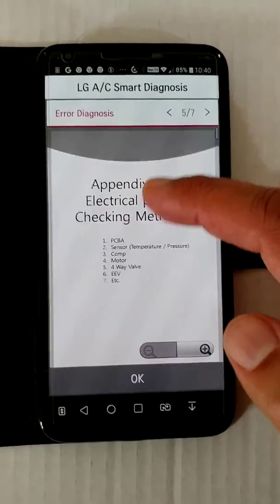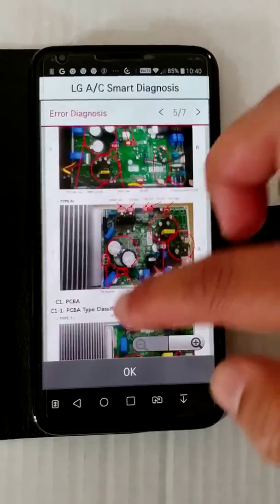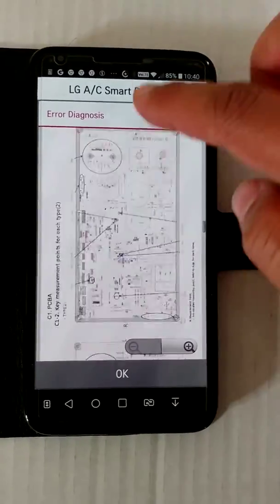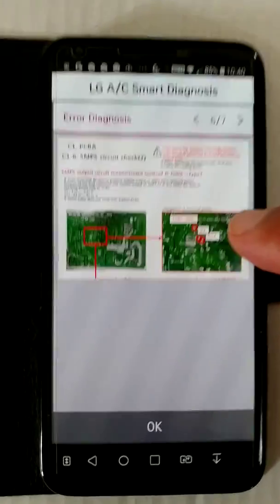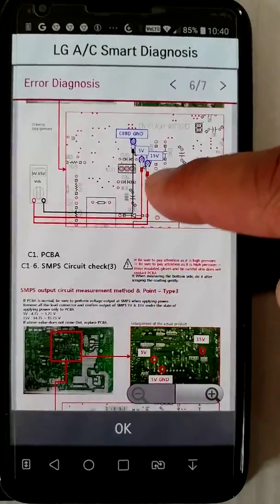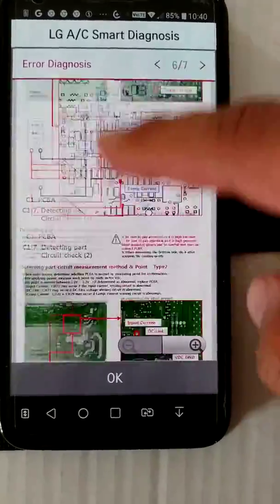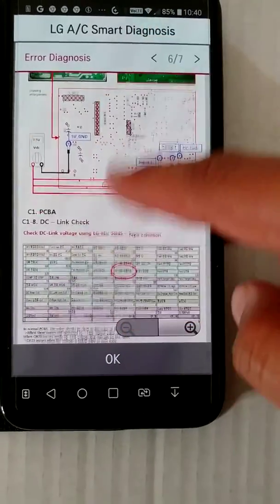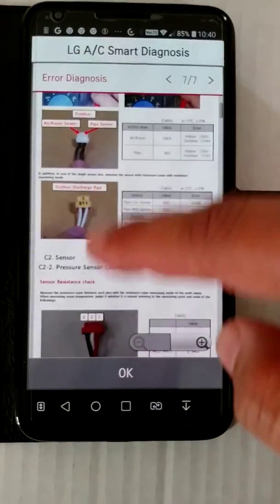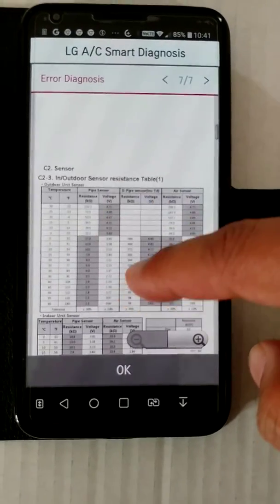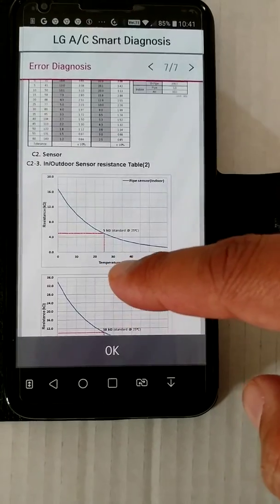The app shows the circuit board, its components, and what to measure if there's a fault. Further pages show switch mode circuitry — more information than you might need, but certainly useful for the air conditioning technician. The last page has thermistor data: indoor thermistor, outdoor thermistor, indoor pipe thermistor, outdoor pipe thermistor, and outdoor discharge temperature thermistor — with temperature profiles and corresponding resistance values to test whether a thermistor is faulty.